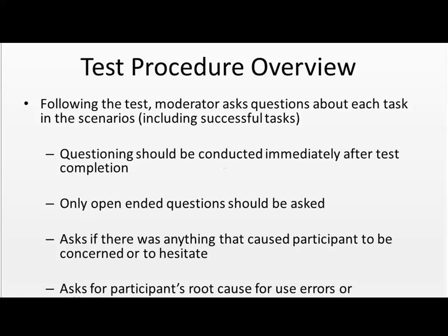Preferably, only open-ended questions are asked. You ask if there's anything that caused the participant to be concerned or to hesitate. You ask for the participant's root cause for use errors or difficulties. If he had a difficulty, why did he think he had that difficulty?